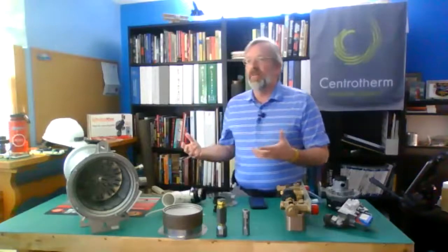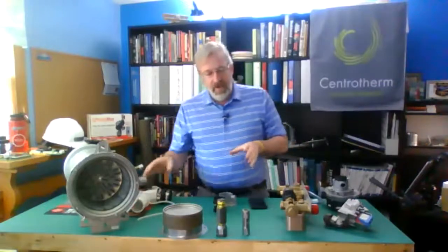Why? Because I'm influencing my gas valve. And I'm going to influence it, especially when you're doing domestic hot water. Over the weekend, it was nice. It was 70 degrees. It was outstanding. And then it's 40 degrees at night. The air weighs a different amount. So as I'm pulling air through my pipe with my fan, the amount of air I'm pulling will change even though the RPM remains the same, just because of air density. And this guy's adjusting my gas valve for that. It's making some little adjustments.